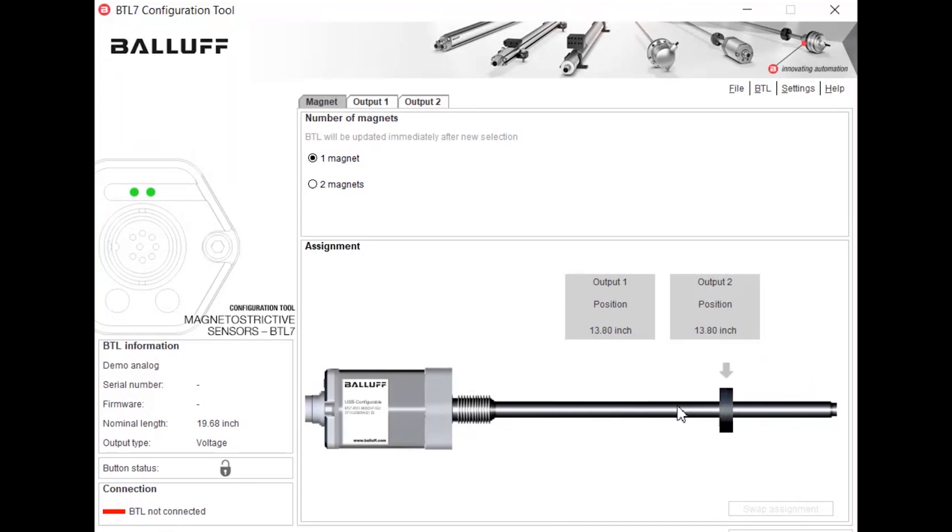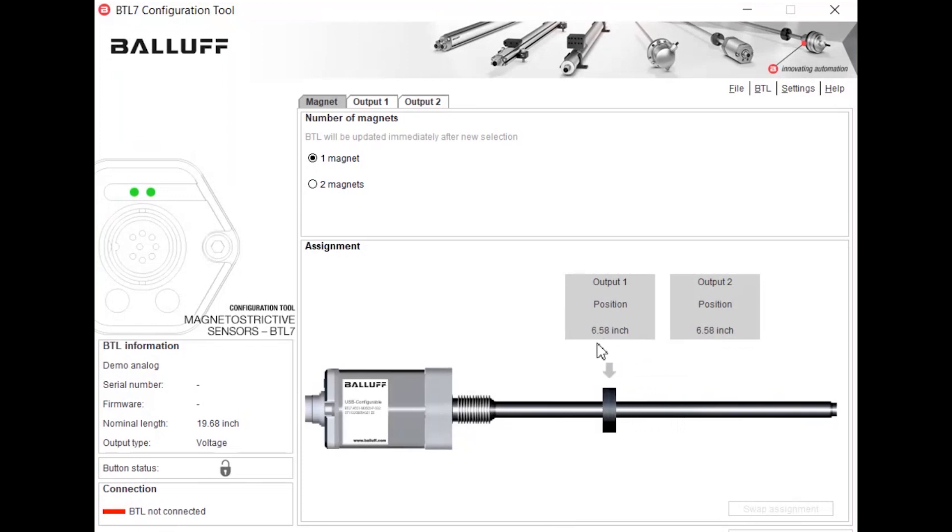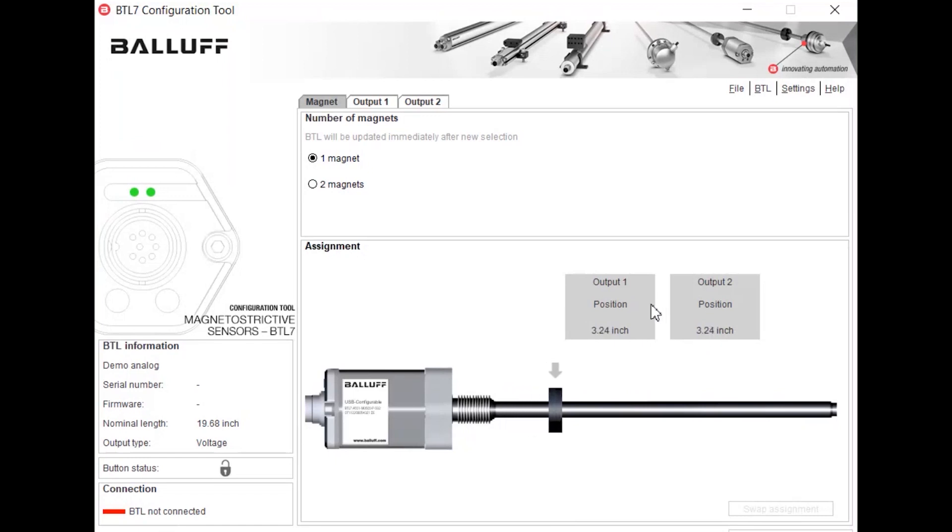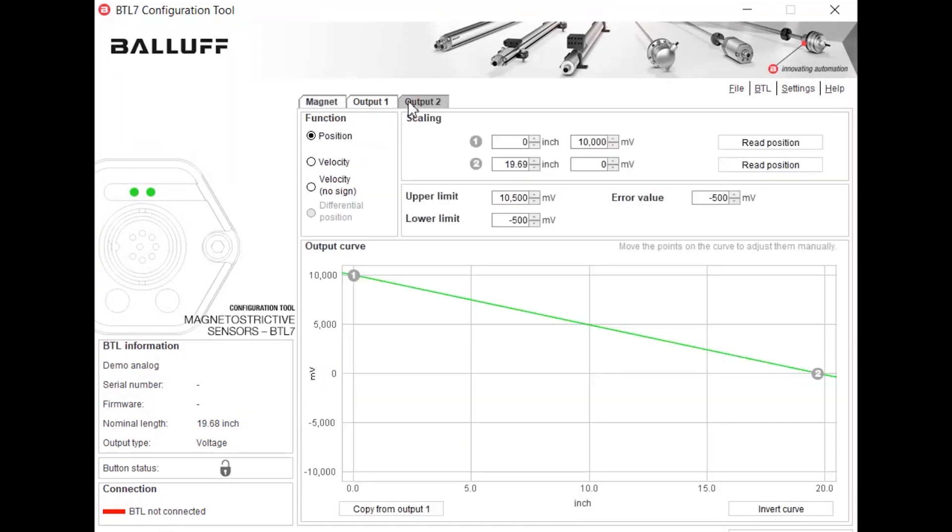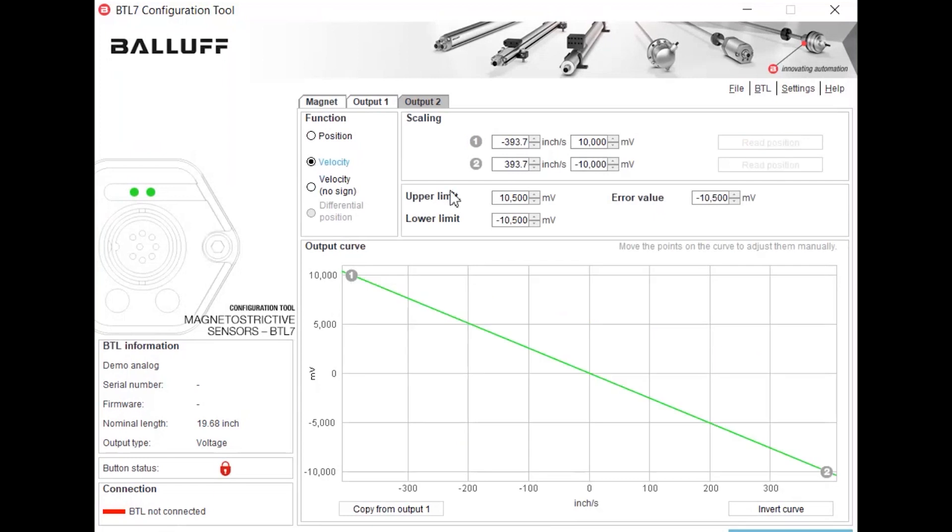As you can see here we're getting a visual of a magnet traveling across the BTL and you can have up to two outputs or measurements on one magnet. Right now they're both reading position but up here we can go ahead and we'll change that second output to a velocity. And again you can also do a velocity with no sign.